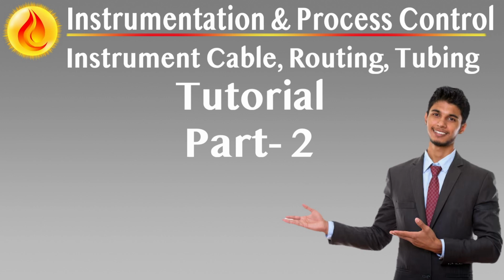Underground trenches for cable routing and environmental protection. Dedicated underground trenches provide superior mechanical and thermal protection for multi-core instrument signal cables. Trenches must be designed with sufficient depth to avoid traffic-related damage and positioned above groundwater level where feasible to minimize long-term cable degradation. Routing must be marked with surface indicators and documented with cross-sectional drawings indicating layout, depth, and cable groupings. Signal cables in trenches may be laid without spacing for signal classes 1 to 4, optimizing space utilization.